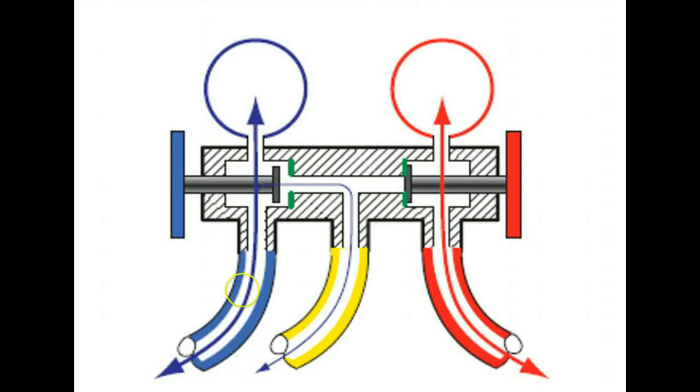So when you're ready to let some refrigerant charge into the system, you're going to slowly back off your suction side valve. You'll do that by turning the knob counterclockwise. And now you've opened up the center part of this manifold to the low side. So you're going to have refrigerant coming from the jug because the pressure in the jug will normally be higher than the pressure on the low side of the system. And it is going to go through this open valve and down into the system. And now you have refrigerant charging into the low side.